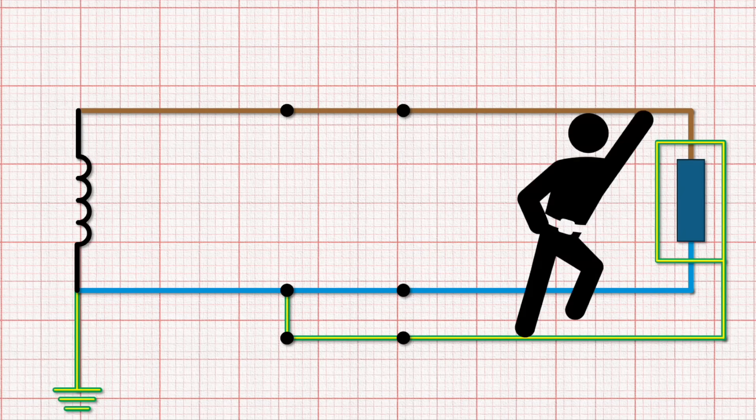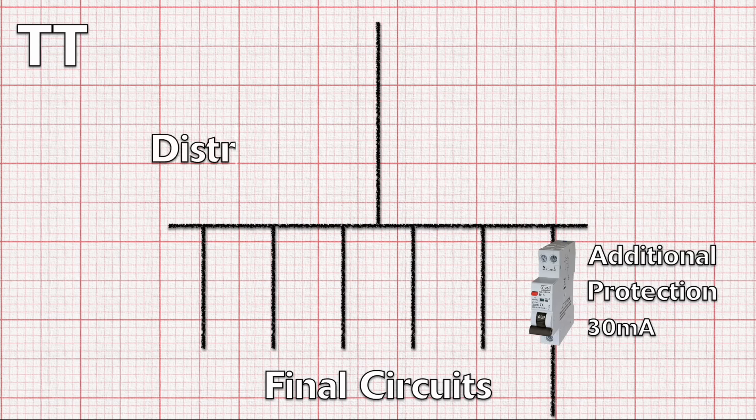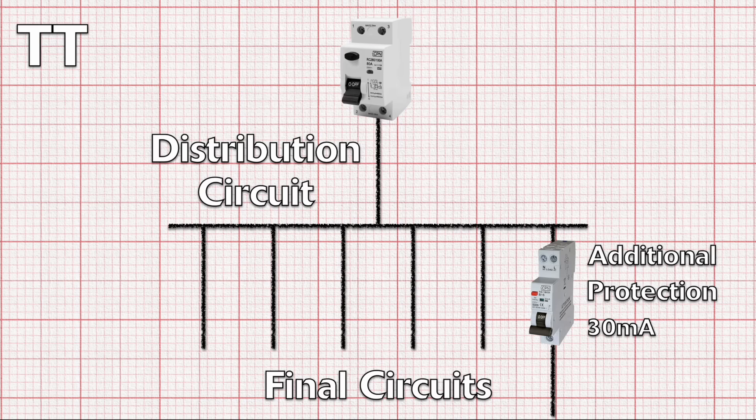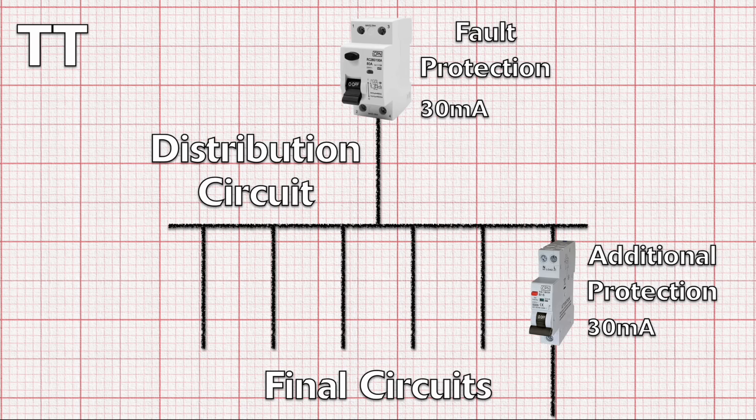But what about if this final circuit is connected from a sub-main or a distribution circuit supplying lots of other circuits? A problem arises here because we need to use an RCD to provide the sub-main with fault protection. If this RCD is rated at 30 milliamps then we run into an issue with selectivity.